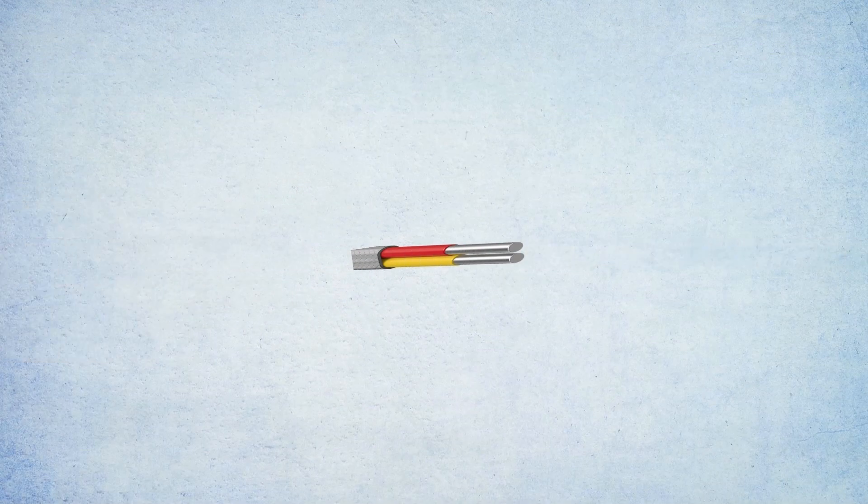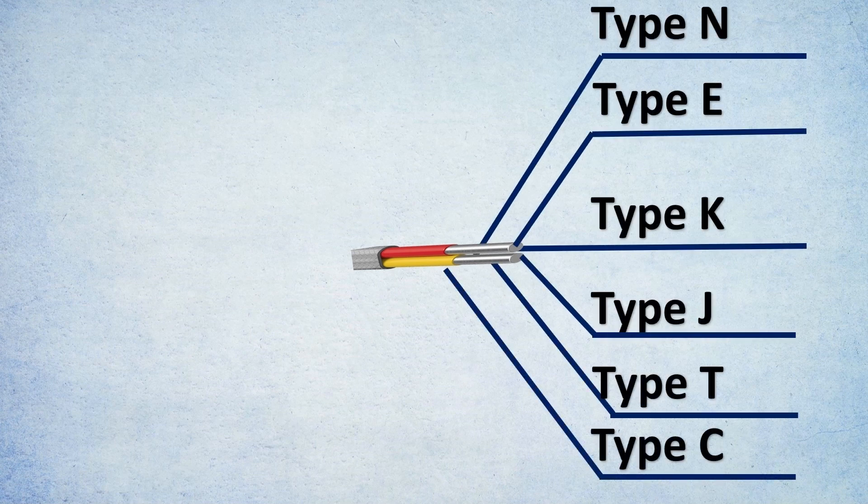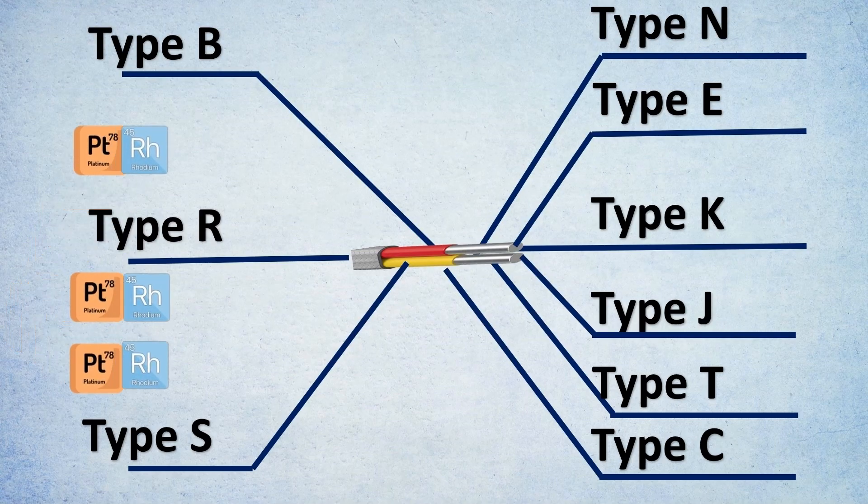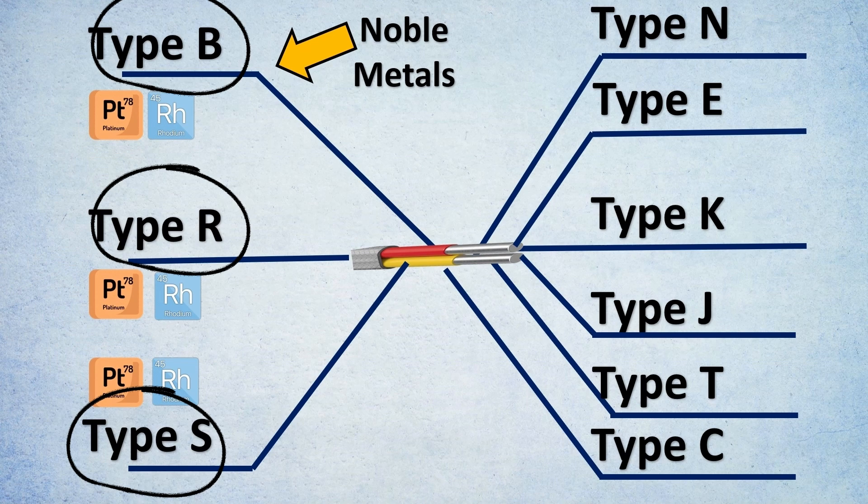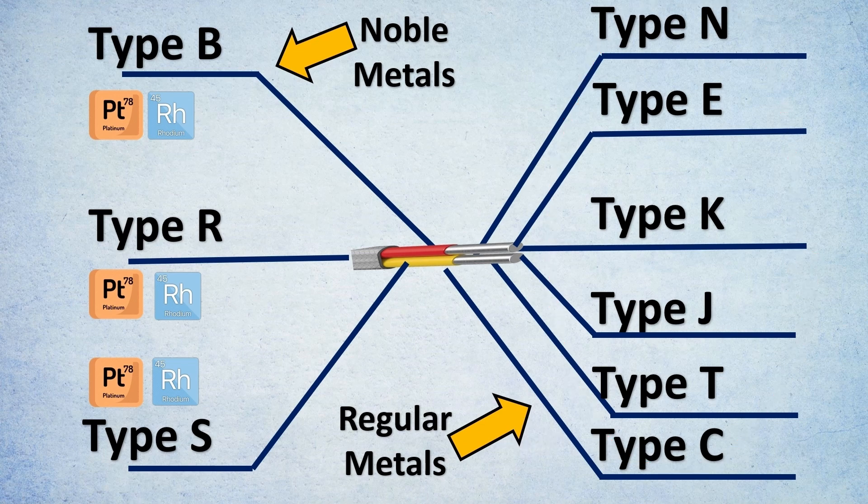Thermocouples can be divided into various types based on metal configuration. The most common is Type K, but you have many types like N, E, J, T, C, B, R, and S. Let's divide them: the three on the left (B, R, S) are made of noble metals like platinum and rhodium in different proportions and configurations. These are preferred only when other regular metals are not applicable.